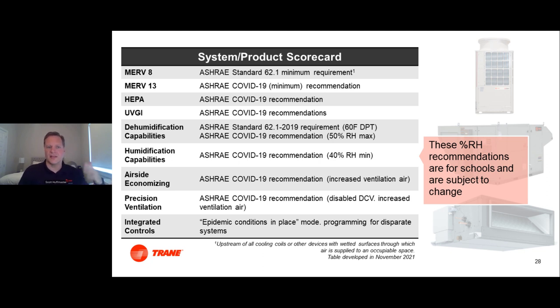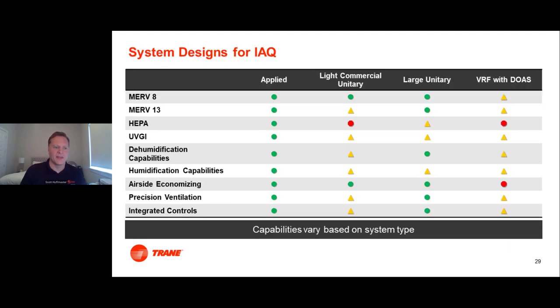So what I want to call out now, as we think about the aspects of a system design that we would ideally have, from a general statement, is how well can different system types handle these recommendations? So really what I'm showing here is whether you're looking at an applied system, a light commercial unitary, a large unitary system, or maybe a VRF system with a dedicated outside air unit, the capabilities of adding these modes and these abilities really vary based on system type. As you'll notice, an applied system allows a whole lot of variability in what we can deliver to a space. A lower cost light commercial unitary system is going to have some struggles with that. HEPA, for instance, we show as a red dot because, to my knowledge, there's not a standard off-the-shelf rooftop unit that can handle the pressure drop of a HEPA added without some form of a fan modification. Most often, if you have a light commercial system and you wanted HEPA, it'd probably be a portable you put in the space and it wouldn't be designed into the system.